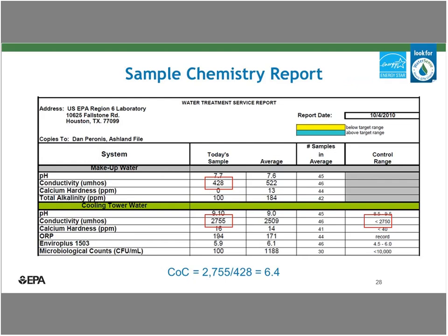This here is an excerpt from a pretty typical water treatment report. The format of these reports can differ, but the information is usually the same. So it includes conductivity of the makeup water. You can see that at the top there, 428. You also have the conductivity of the cooling tower water. This is the same as the blowdown water that gets blown down. So for this system, it's 2,755. Dividing the blowdown conductivity by the makeup conductivity gives you a little over 6 cycles. So in this case, it's not bad.